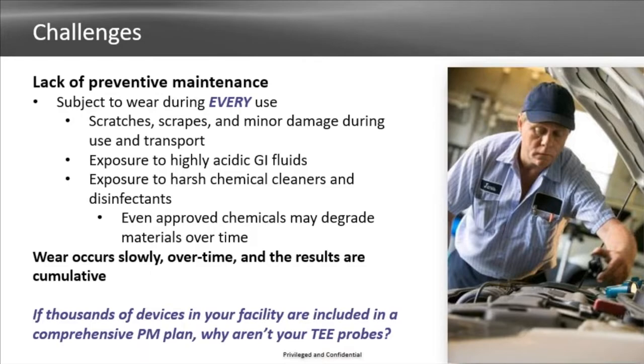But they say, well, the patient's out, so I don't need to use a bite block. Well, even if the patient's out, they can still have a gag reflex and can clamp down on that probe. They still have teeth, at least most of them. If somebody has false teeth, they're asked to take them out prior to an exam, but most people have teeth, and they can either bite down or just the act of inserting this probe into a patient's mouth and dragging it across the teeth will cause damage. That's how fragile they are.